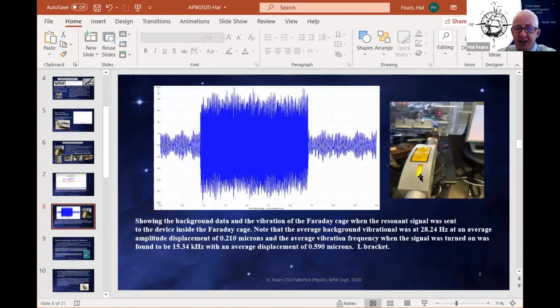So what happened? I'll show you what happened. So I was shining the vibrometer right at the Faraday cage. So here's nothing happening, and here's where I switch on the 35 kilohertz pulse. Suddenly it jumps a little bit. But remember, there's no isolation going on here. This is directly onto the Faraday cage. And what I'm seeing is the displacement's increasing, obviously, but it's very small. And notice the frequency is actually quite different to the 35 kilohertz. So the background vibration I see here is 28 hertz. So that's the background frequency. And the average amplitude of this little noise here is about 0.2 microns.